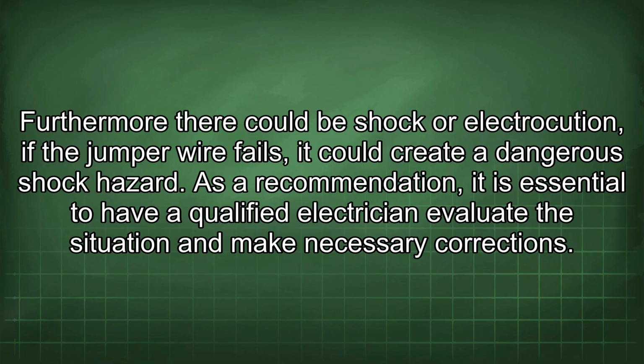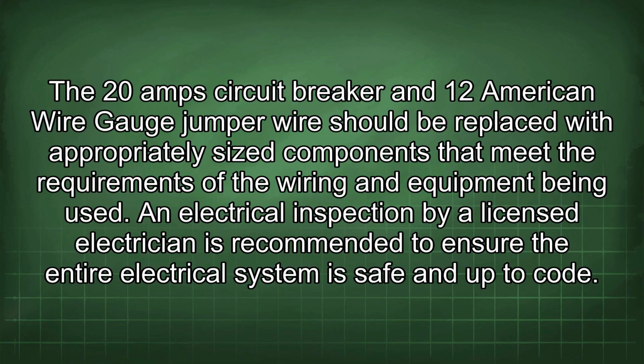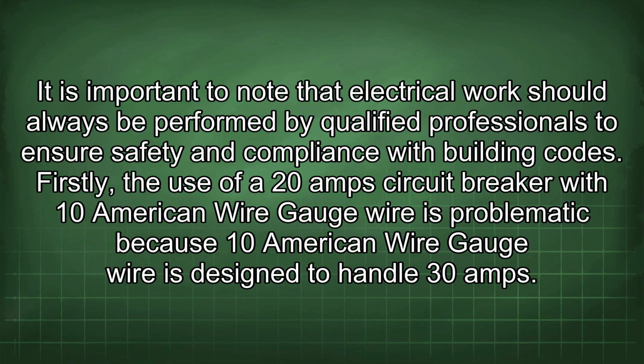As a recommendation, it is essential to have a qualified electrician evaluate this situation and make necessary corrections. The 20 amp circuit breaker and 12 American wire gauge jumper wire should be replaced with appropriately sized components that meet the requirements of the wiring and equipment being used. An electrical inspection by a licensed electrician is recommended to ensure the entire electrical system is safe and up to code. It is important to note that electrical work should always be performed by qualified professionals to ensure safety and compliance with building codes.